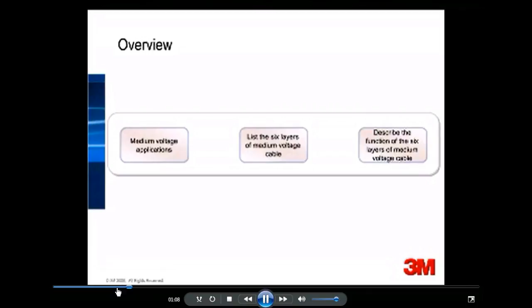Medium voltage cable is electrical cable with a voltage rating of 2 kilovolts to 46 kilovolts. When we start talking about high voltage and low voltage, the voltage level depends on the application. In housing, we call 240 high voltage and we call 120 low voltage. When we start dealing with cables and transmission, then low voltage is usually considered anything below 2,000 volts. And then medium voltage is from 2001 volts up to 46 kilovolts, and anything such as 69 kilovolts is considered high voltage cable.